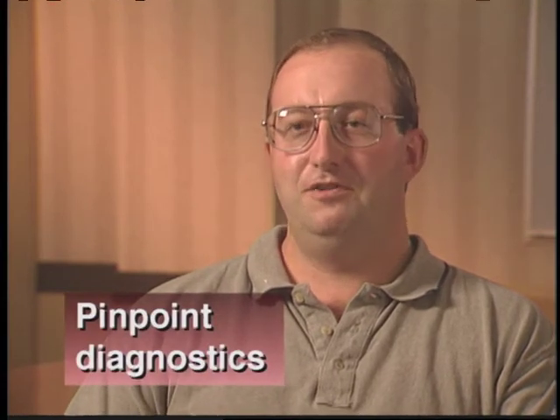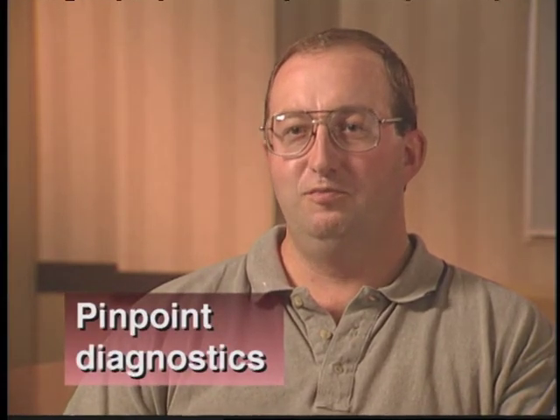As far as troubleshooting transmitters, DeltaV and the little blue bar below the detail is one of the best things I've ever seen, from the standpoint that if I get called in for a control problem, and control guys everywhere I think will tell you, boy, they see a lot of software problems that aren't software. If you've got that little blue bar below the detail, it's not a software problem. You're getting a bad reading in from the field. And many times, we can look at that and tell you, hey, you got a blown fuse, or the transmitter's under range or over range, or there's something wrong in the field. It's not in the software.